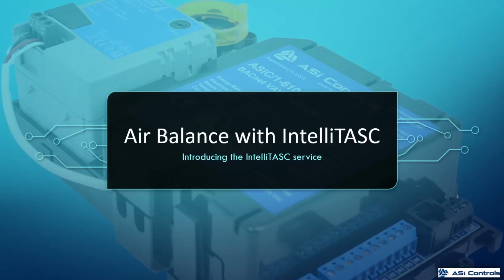One of the really nice features of IntelliTASC is the ability to do air balancing of the 6100 controllers directly from the Niagara interface. This gives you a nice central point to do the air balancing from. And if you're very familiar with the ASI Expert air balancing interface, then you're going to be very comfortable with this one as well, because it's not very different. So let's have a look at it.